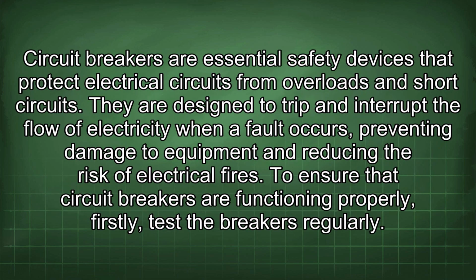Circuit breakers are essential safety devices that protect electrical circuits from overloads and short circuits. They are designed to trip and interrupt the flow of electricity when a fault occurs, preventing damage to equipment and reducing the risk of electrical fires. To ensure that circuit breakers are functioning properly, firstly, test the breakers regularly.